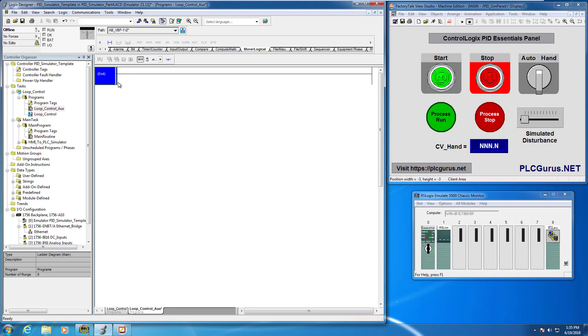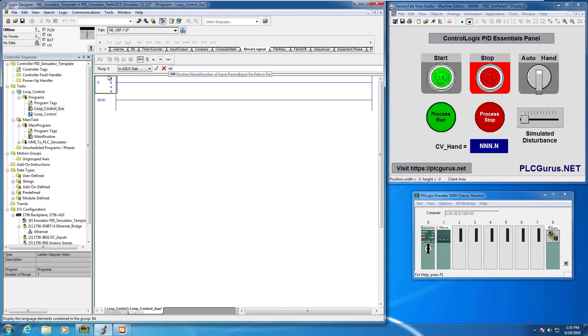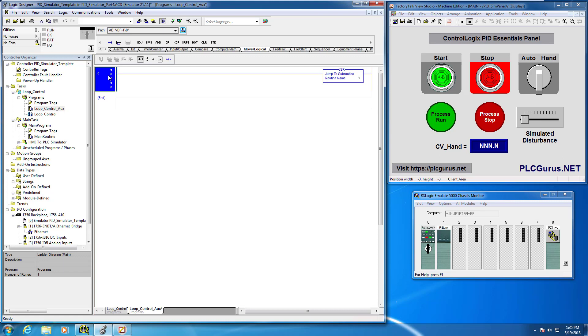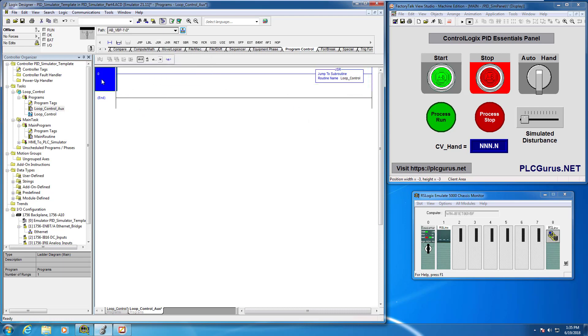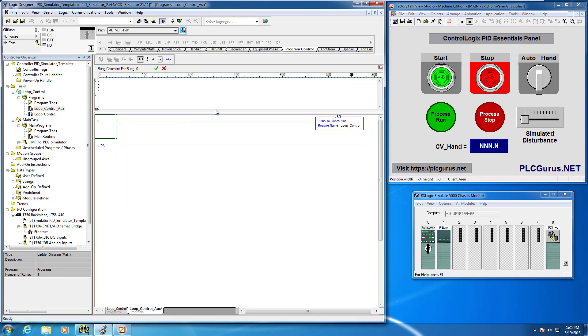The first thing we want to do is add a jump-to-subroutine instruction so we can jump from the main routine in this task program into the loop control routine where our PID loop will be processed. I'll add a new rung and type in JSR — that's how you add instructions if you know the shorthand abbreviation. We want to jump to the loop control function block routine and we'll give it the rung comment: 'function block diagram subroutine for PIDE processing'.